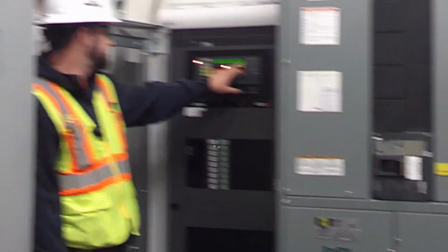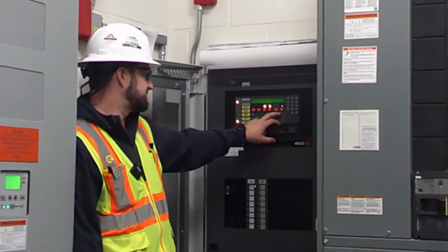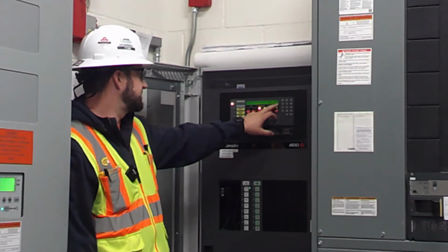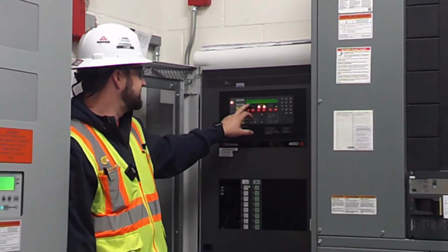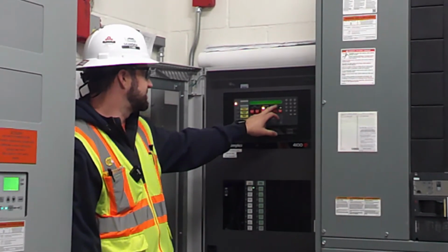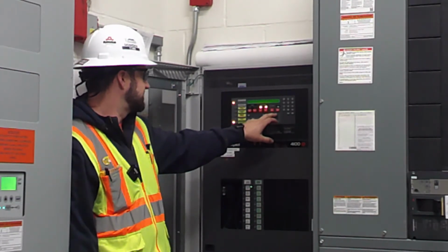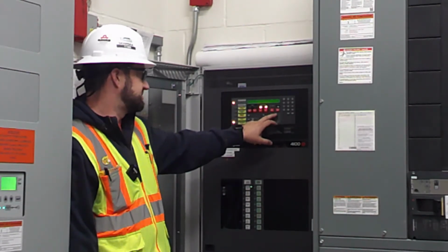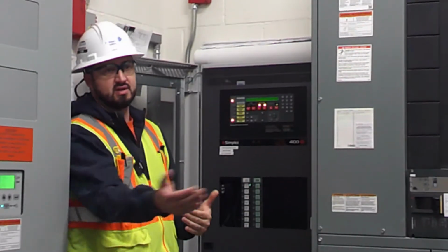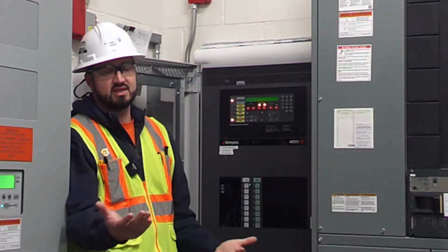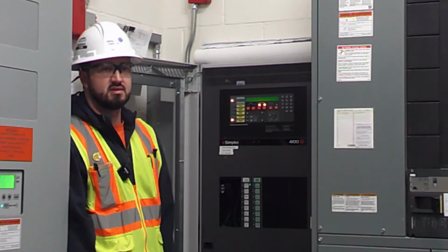If you scroll through, everything is addressable, not just the smoke detectors, but also the strobes. So it's smart enough to tell you that D, second floor hallway in the entrance, has no answer on that strobe. These are all just a bunch of strobes because there's one break in the circuit. They just need to tie a device in, but they can't get to it because of the carpet being installed.